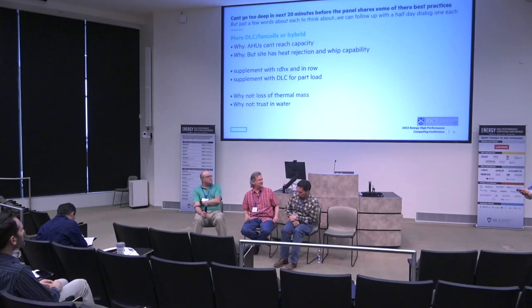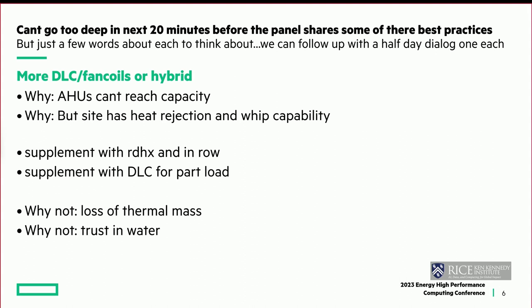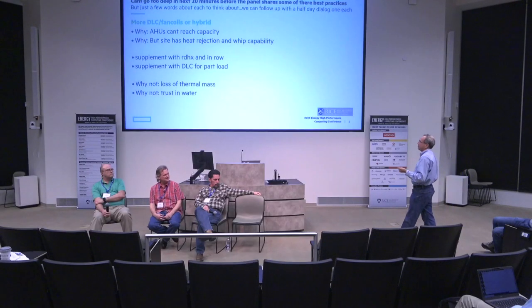Because you have liquid in your data centers already, it's just at the perimeter. Most of the time, unless you've got a package air handler or a rooftop DX unit, you've got liquid in your facility, it's just at the perimeter. So now you start to bring it into the rack, whether it's a rear door heat exchanger, a sidecar heat exchanger, or DLC in the rack.